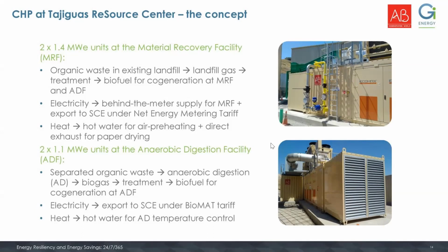The MRF generates quite substantial electrical loads to process that separated waste, and that's where the cogen unit comes into play. There is sufficient load at the facility for the cogen unit to supply on-site electricity and export surplus electricity to the grid, available through a net energy metering tariff for renewable-fueled cogen units.